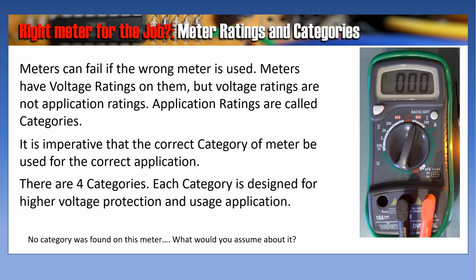So what is the right meter for the job? Well, meters have ratings and categories. Meters can fail if the wrong meter is used. Meters have voltage ratings on them, but the voltage ratings are not application ratings. Application ratings are called categories. It is imperative that the correct category of a meter be used for the correct application.